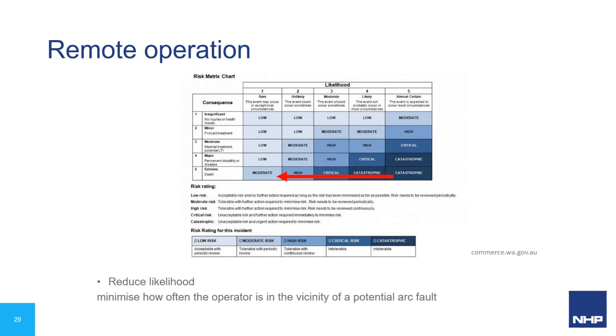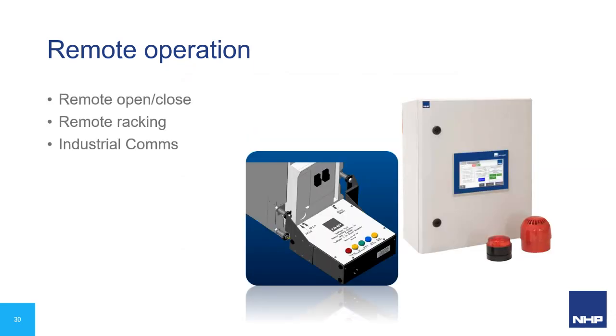So let's have a look at what our options are there. Remote open and close: tripping coils, closing coils, circuit breakers, motor operators, all very, very available these days. Remote racking in high voltage has been around for a very long time for withdrawable switchgear. For low voltage, we've actually got quite a lot of that coming through now. So the NHP system there is in the middle. And the other one, which seems to be underutilized a bit, is industrial communications. Practically every bit of switchgear out there is now available with a communications variant. So you can pull all that information back to outside of the room, to a control room, whatever it is, and do whatever you need to with that information, make any decisions you need to.